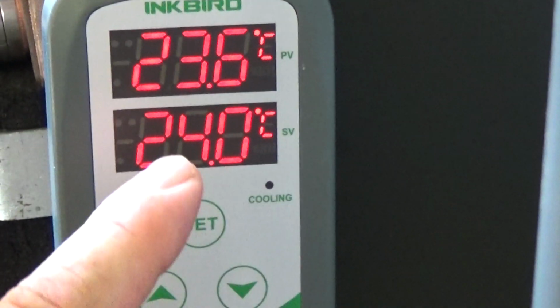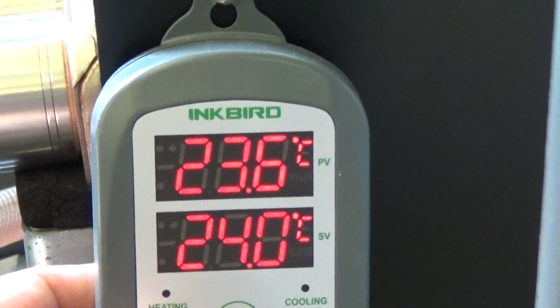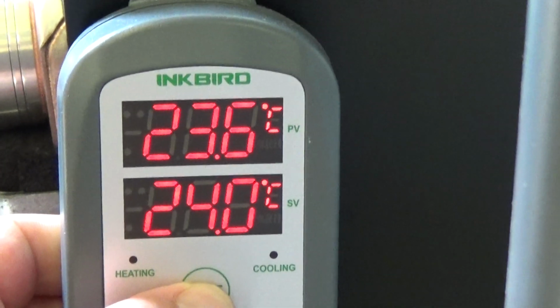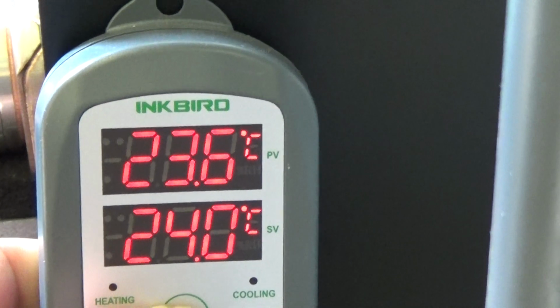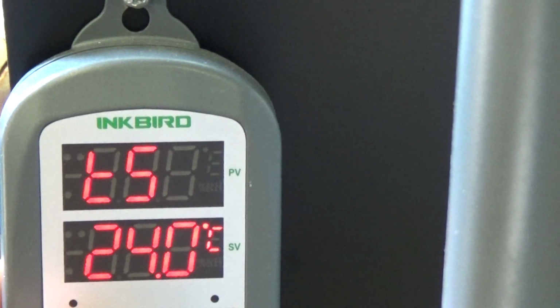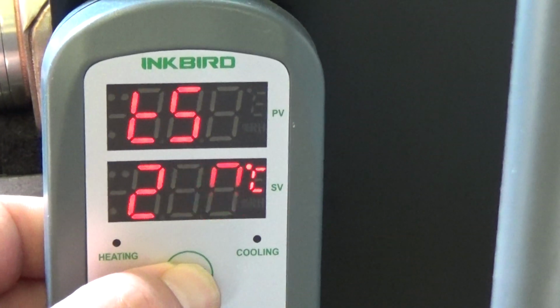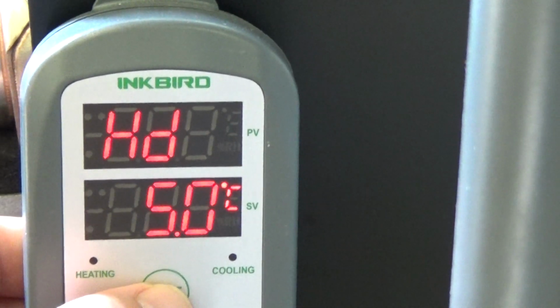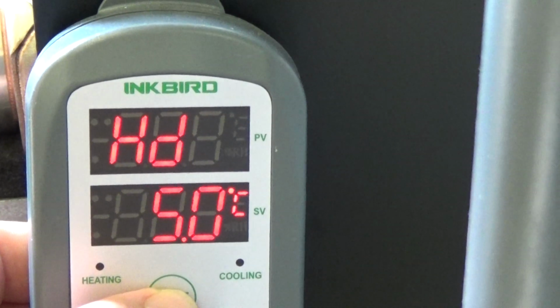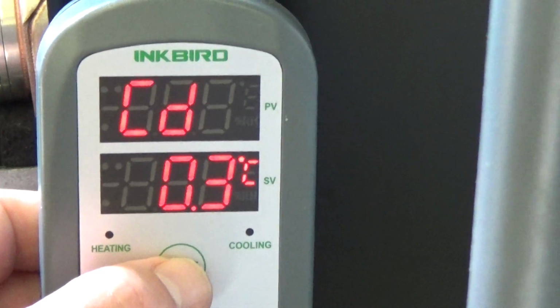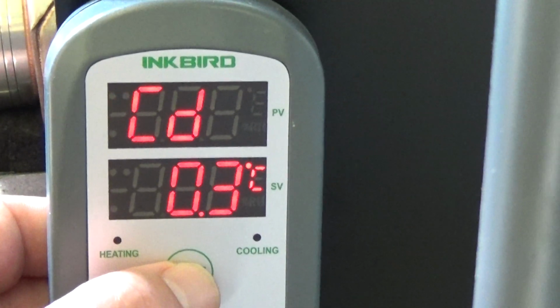With the Inkbird controller, the bottom is our set point. When you go through the parameters, you hold set for a couple seconds. That's your temperature set point. You press set again. That's your heating differential. We're not in heating mode, so that's not applicable. Our cooling differential, you can see we have at 0.3 degrees C.